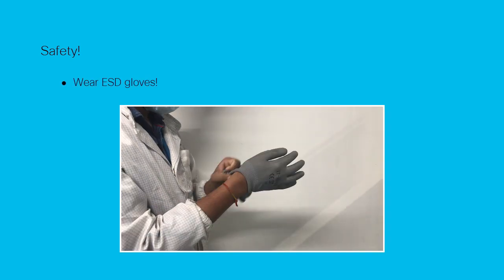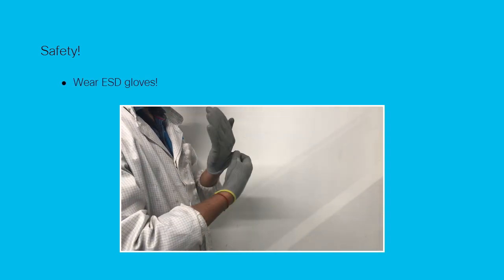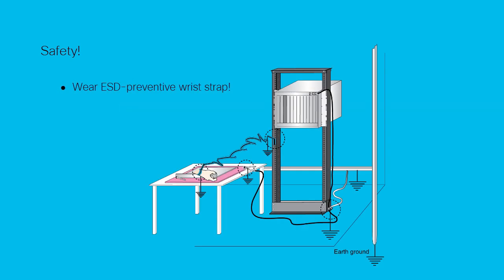You must wear ESD gloves to prevent electrostatic discharge. Wear an ESD preventive wrist strap and attach its end to a grounding terminal. If the grounding terminal is on the chassis, ensure that the chassis and the rack on which it's mounted are also grounded.